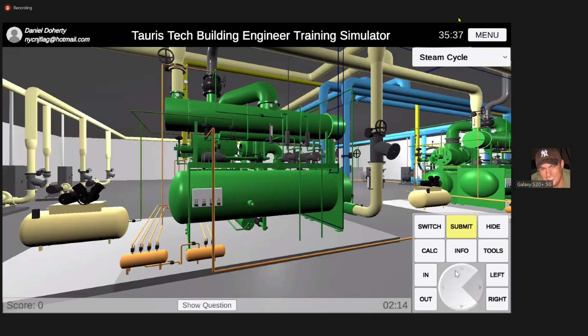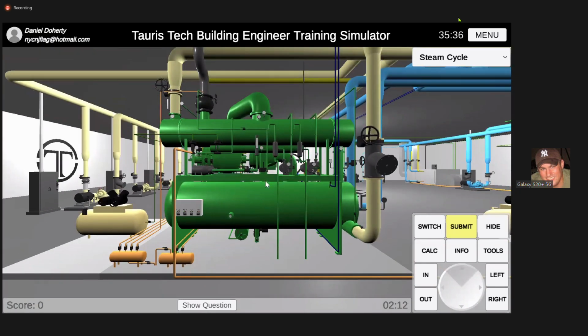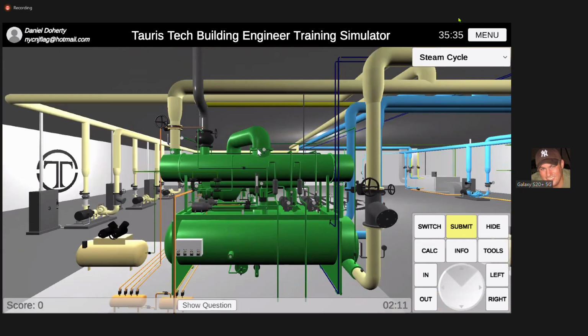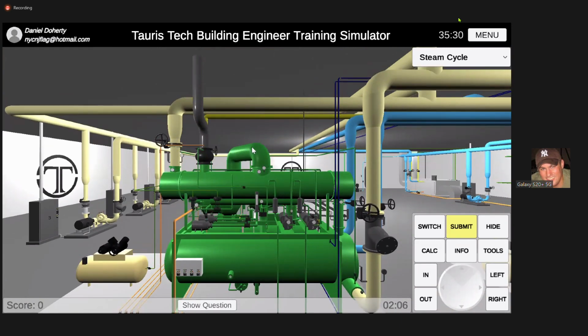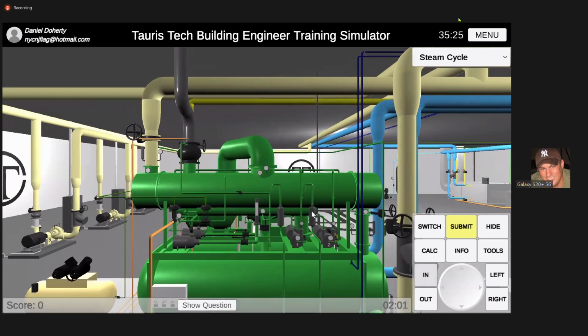So again, you got your turbine exhaust pipe right here. That turbine exhaust has steam in it. That steam comes into the shell, and that steam hits those pipes with the cooling water in it. Okay? When the steam hits the cooling water, it starts to condense. What helps the steam draw this way is that it is under a vacuum. That's what the vacuum pump's for. The vacuum pumps are pulling. Okay? So the steam comes in here, it condenses, it goes to your hot well.